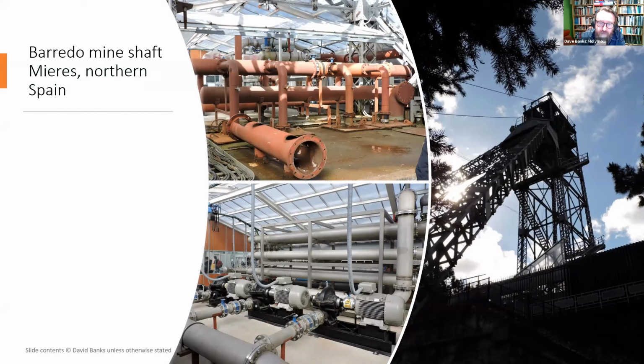I think they pump about 200 litres a second of mine water. Then they put it through massive shell and tube heat exchangers, shown in the bottom left photo, to exchange heat with the mine water. They manage to supply heating and cooling to a major regional hospital, a university, and several other buildings. It's about 5 or 6 megawatts of installed capacity, I believe. There, the mine water quality is so good they don't actually need to treat it.